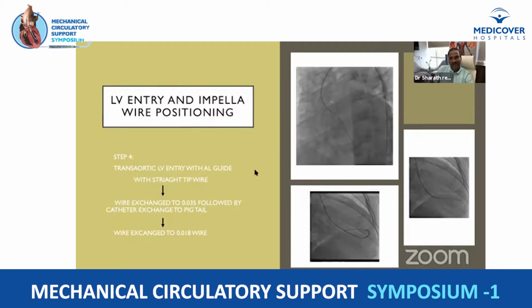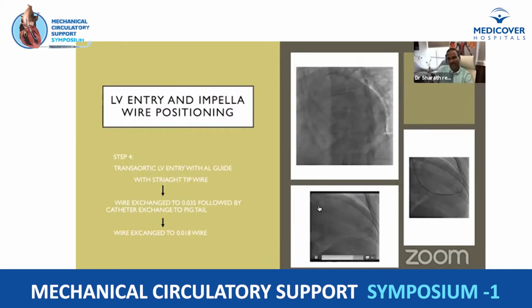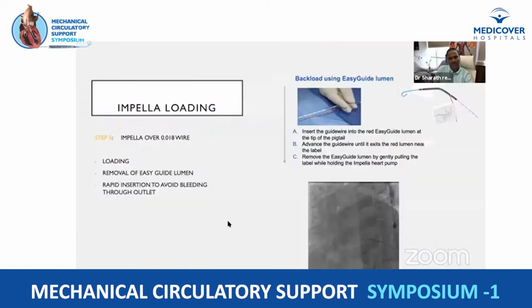So we can enter the LV with the Amplatz AL catheter with a straight tip wire, and then push the catheter into the LV, and then exchange the catheter to the pigtail, and then take the 018 wire, which is there in the Impella kit, after giving a good loop at the tip, and position it along the apex into the LV. So once the 018 wire is in the LV, then go to your next step, that is Impella loading.